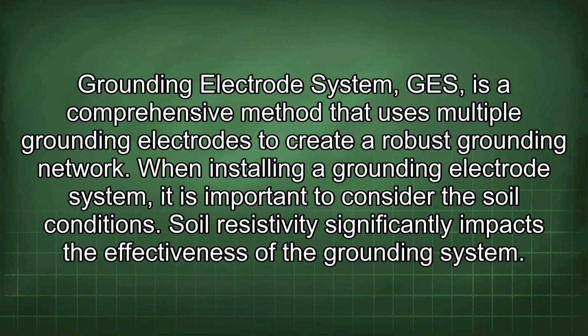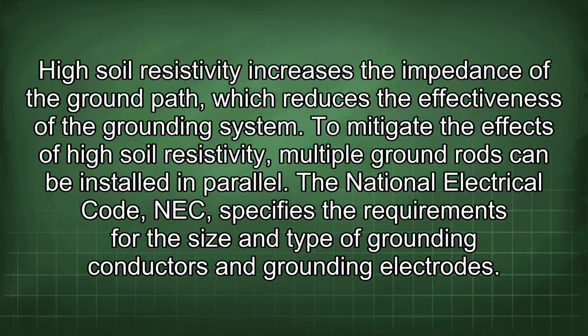Grounding electrode system (GES) is a comprehensive method that uses multiple grounding electrodes to create a robust grounding network. When installing a grounding electrode system, it is important to consider the soil conditions. Soil resistivity significantly impacts the effectiveness of the grounding system. High soil resistivity increases the impedance of the ground path, which reduces the effectiveness of the grounding system. To mitigate the effects of high soil resistivity, multiple ground rods can be installed in parallel.